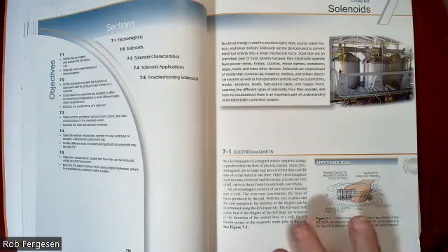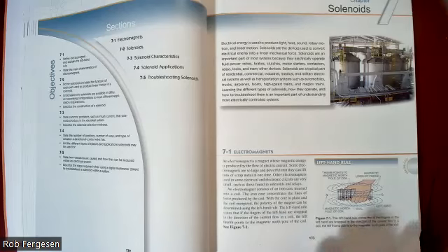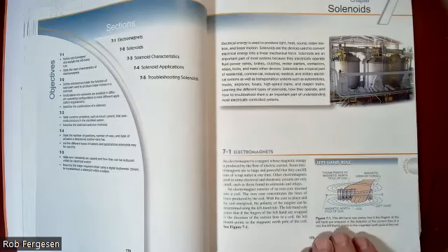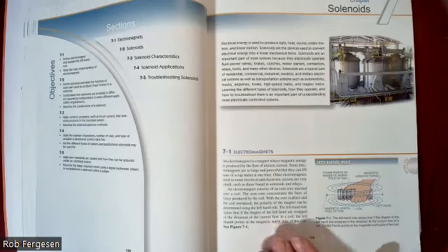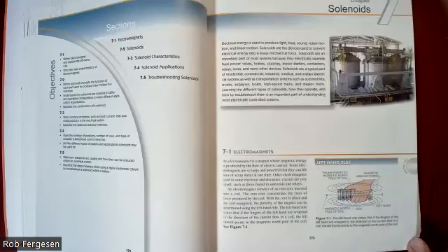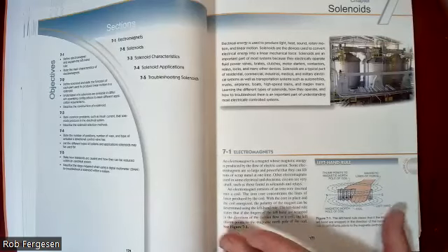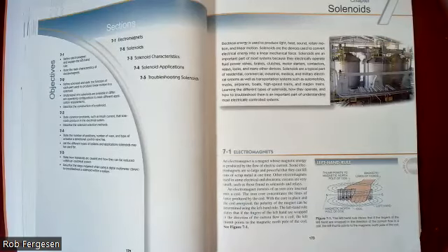So you're going to find these embedded inside of PLCs. We have little bitty optically isolated relays with tiny solenoids that control voltages straight out of a PLC. So they're built into the motherboard of a PLC. And you're going to find them built into panels where we're controlling with a small PLC a much larger voltage that will screw up the PLC. And of course, you're going to see these in virtually every motor starter circuit.